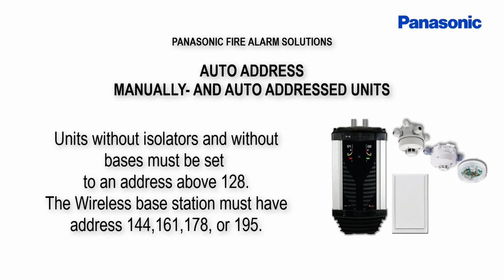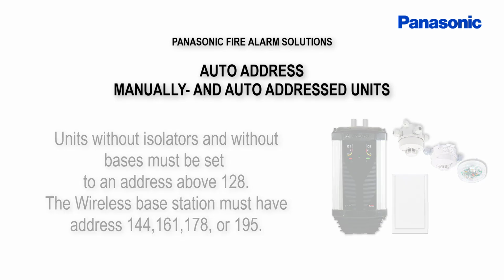Units without isolators and without bases must be set to an address above 128. The wireless base station must have address 144, 161, 178, or 195.